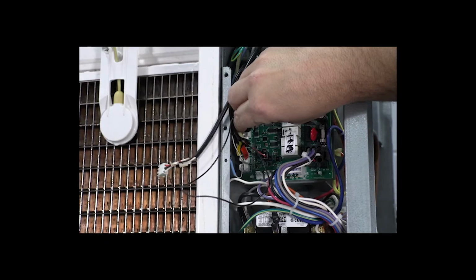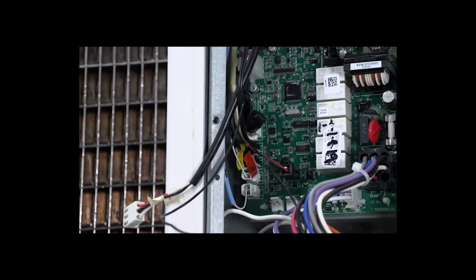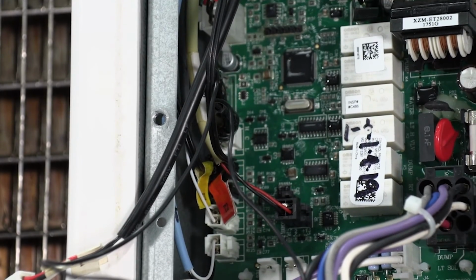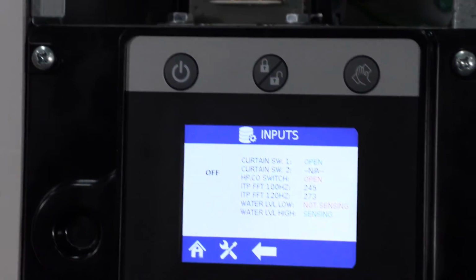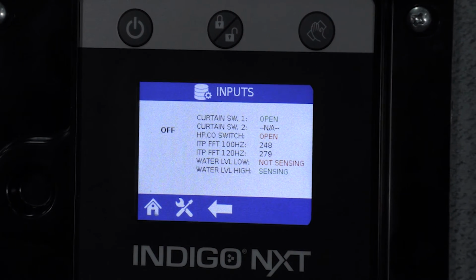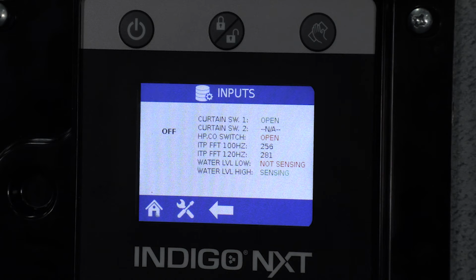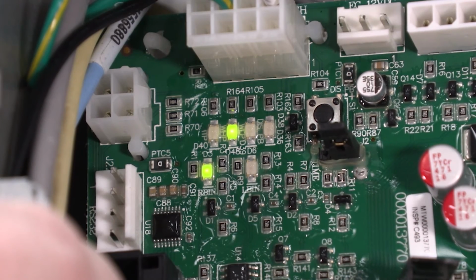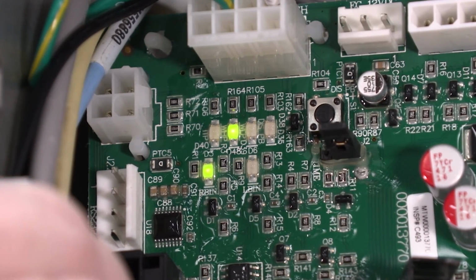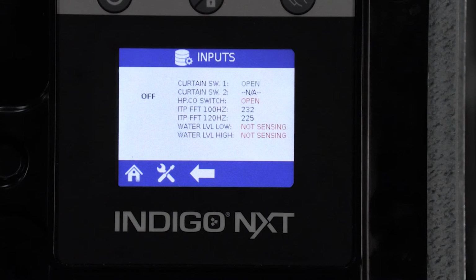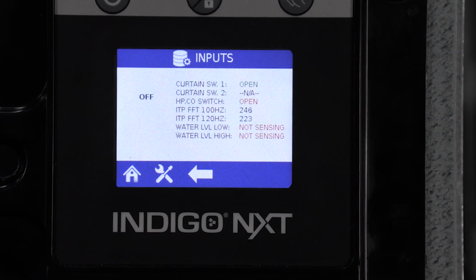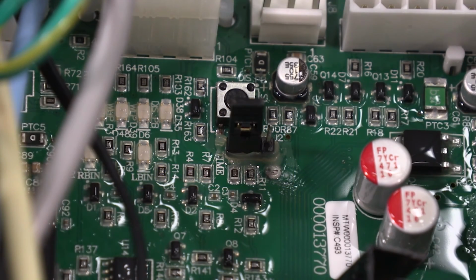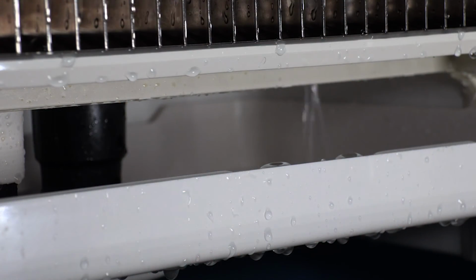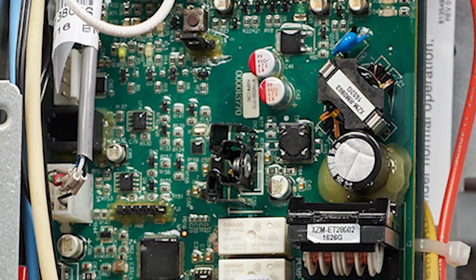If you wanted to verify the control board is not the problem, jump out the water level probe with a jumper wire. If the ice machine functions normally while doing this, it verifies the rest of the system is operating properly. Wait until the pre-chill cycle begins, then jumper the water level probe connection, C for common, and H for high at the control board. Display should read water level high sensing, water level LED light on the control board should also energize and the water flow should stop. If the user interface display reads water level high, not sensing, and the water level LED light on the control board does not energize while water continues to flow in, then replace the control board.